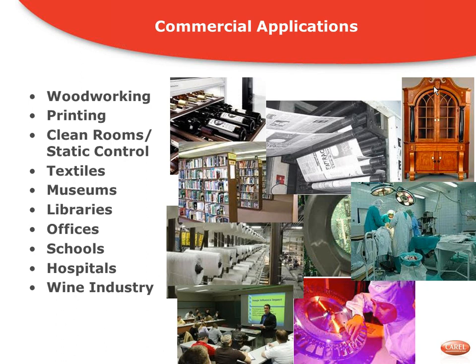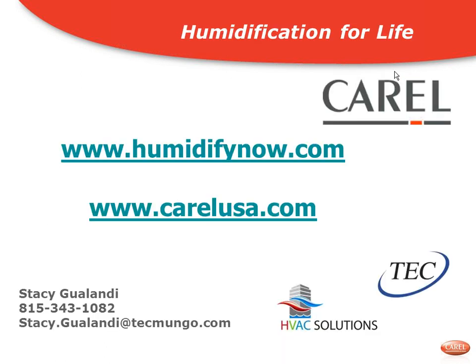So there's a lot of different applications where you can offer your customer a humidification solution where they didn't actually realize there's options out there. They may be relying on the 80-20 system to modulate, as soon as that economizer comes on, everything goes out the window, their design goes out the window. So you can still use a humidification system to tightly control the relative humidity in a space, depending on the season and depending on the load. So there are a lot of things that you can identify and offer to your customer that may be a little bit different. These commercial systems are a lot more precise than residential.